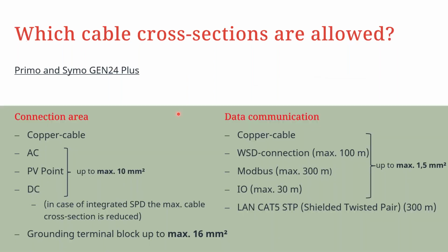In terms of the cables in general, for data communication as well as DC and AC power for the Primo and Symo GEN24 Plus: for the connection area for AC and DC, we require copper cables, for both the AC PV point as well as DC. In case of integrated SPDs, the cable cross section that can be used is affected slightly, so it needs to be reduced slightly. And for the grounding terminal block, as I said before, you can connect a maximum of 16 millimeter cable cross section. For data communication as well, we require copper cables only.